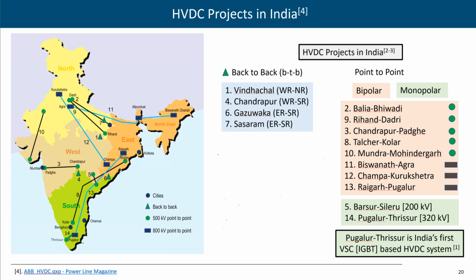But sir, power can flow in both directions, so it should have both combinations, no? Both combinations mean if it moves from first to second, that's AC to DC, then again AC. Now if it's the other way, that is correct too. So suppose I call this first and second: if first acts as rectifier, then second acts as inverter, and if second acts as rectifier, then first acts as inverter. At a time they act as one, but both can perform the role of rectifier as well as inverter. So because bidirectional power is required, both can do both functions, but at a time only one function. So this entire block, if present inside one substation, is a back-to-back converter, back-to-back HVDC.